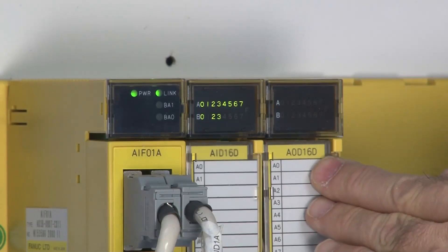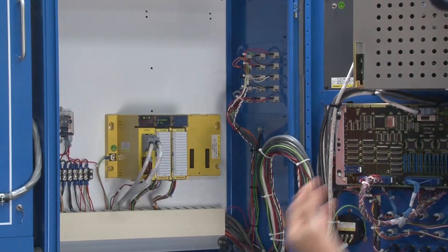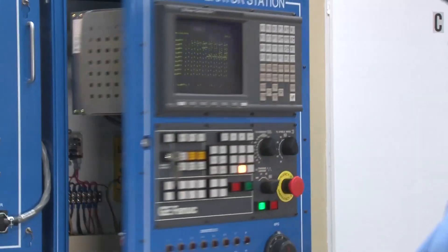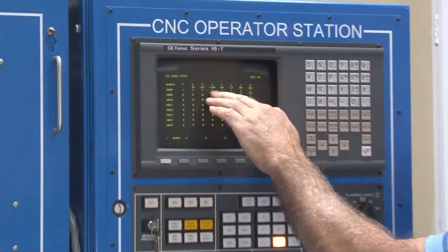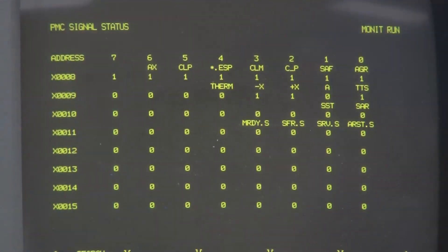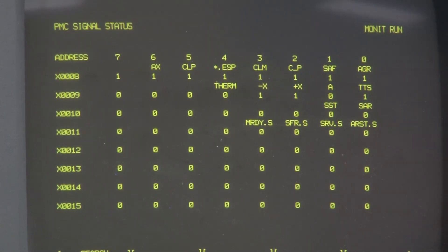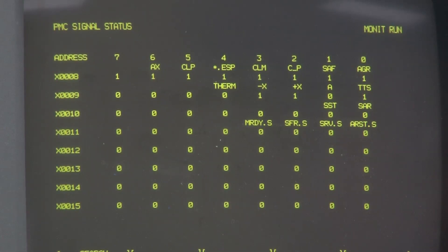The input module has LEDs that will indicate if a signal is currently being applied to it. To make sure that the information is getting from this module to the PMC, you can look at the PMC diagnostics display screen. The diagnostics screen for that particular address will change from a 0 to a 1 to indicate that the PMC is seeing the change in the limit switch.